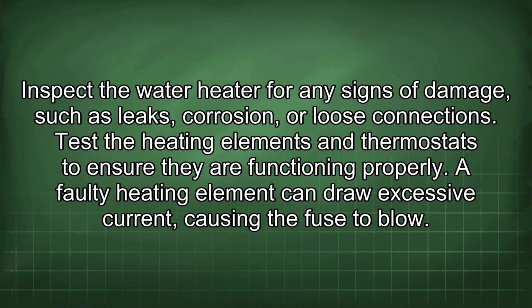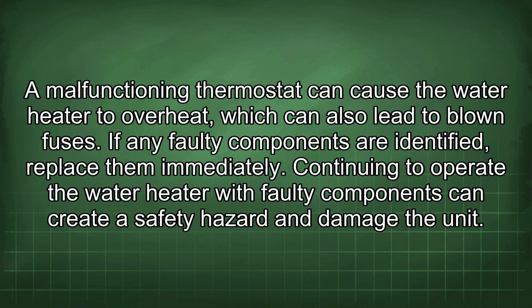Inspect the water heater for any signs of damage, such as leaks, corrosion, or loose connections. Test the heating elements and thermostats to ensure they are functioning properly. A faulty heating element can draw excessive current, causing the fuse to blow. A malfunctioning thermostat can cause the water heater to overheat, which can also lead to blown fuses. If any faulty components are identified, replace them immediately. Continuing to operate the water heater with faulty components can create a safety hazard and damage the unit.